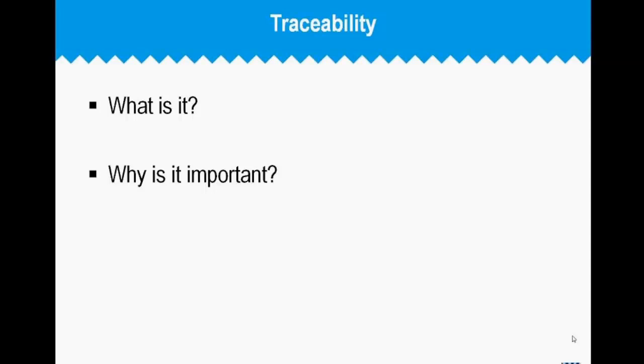It was Metcalfe's law. It's proportional to n squared, so the number of nodes or number of connections in your traceability matrix. Think of a conservative example of take a high-level requirement and trace it to 5 sub-requirements, each of which maps to a procedure in code, and each procedure requires maybe 5 test cases for validation and verification, okay? And when you start to add that up and figure out how challenging that is to maintain, you would have to track the one-to-one and one-to-many and many-to-one mappings from the original requirements through the decomposition to the sub-requirements, procedures, et cetera. And it could get onto several hundred, sometimes several thousand test cases.